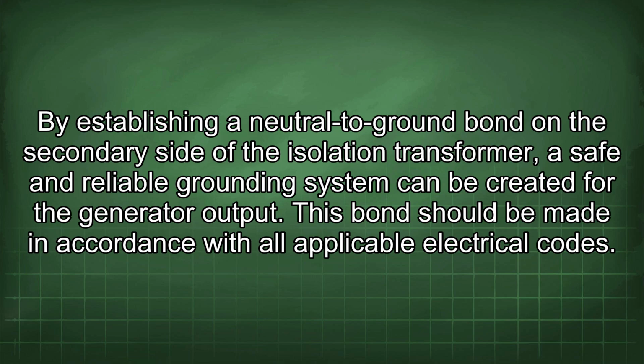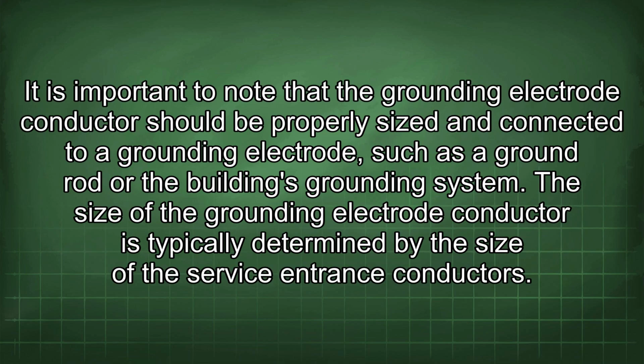This bond should be made in accordance with all applicable electrical codes. It is important to note that the grounding electrode conductor should be properly sized and connected to a grounding electrode, such as a ground rod or the building's grounding system. The size of the grounding electrode conductor is typically determined by the size of the service entrance conductors.